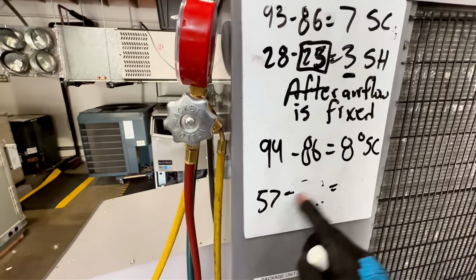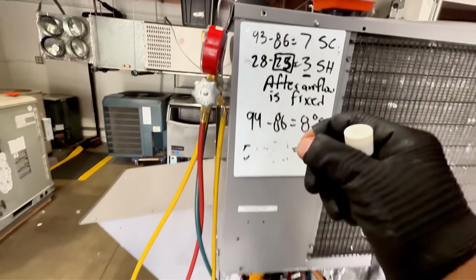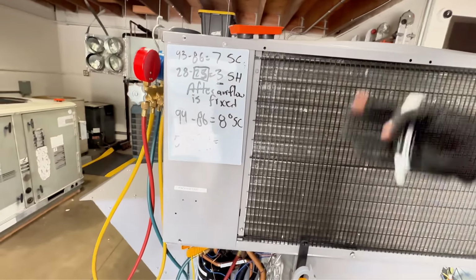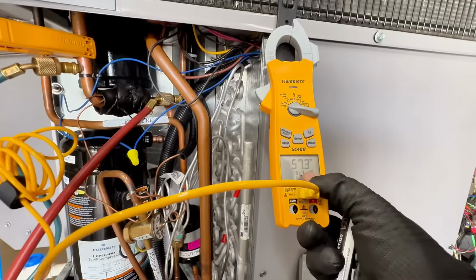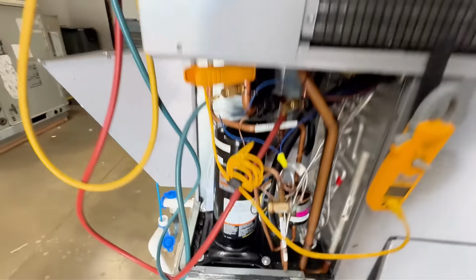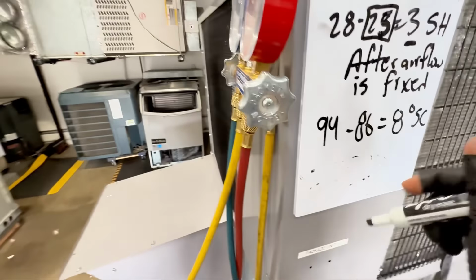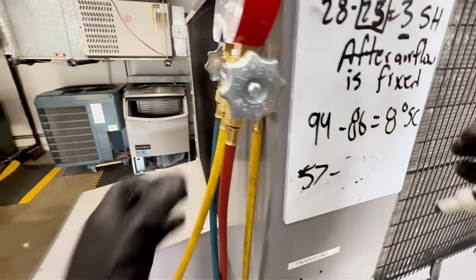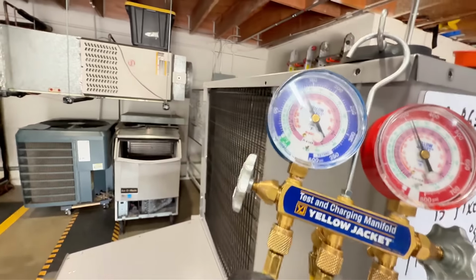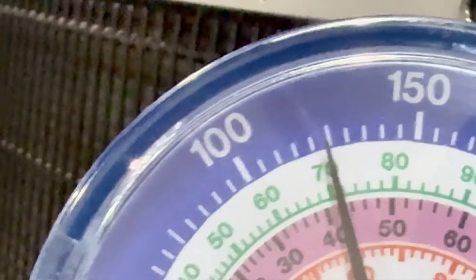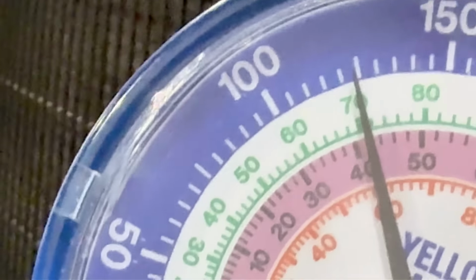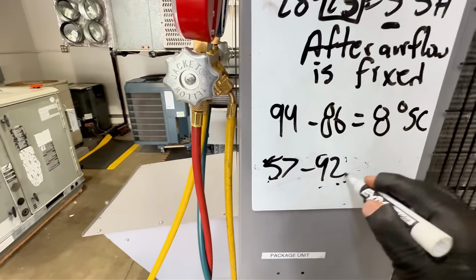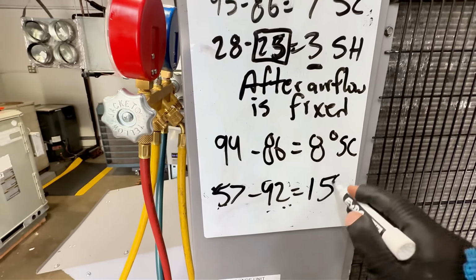So the TXV is adjusting. It's opening up more because it's like, whoa, there's a lot more hot air coming. Give me more food. Give me more refrigerant. So we're still at 57, suction line temperature 57. And then, let's see. I'm at 42. So 15 degrees of superheat.